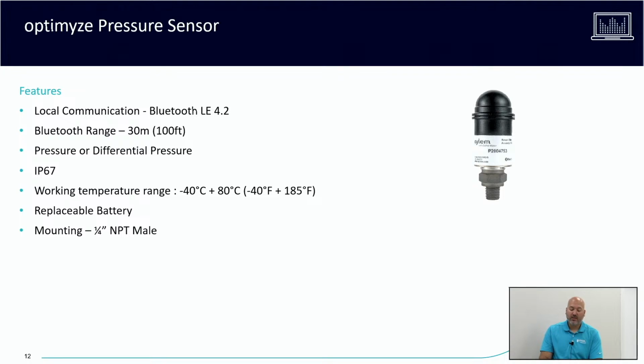Lastly, the pressure sensor. This is once again communicating via Bluetooth to the optimyze sensors. So the pressure sensors will have to be mounted or installed within 100 feet of the optimyze sensors to get that data over. As I touched on earlier, you could measure just suction pressure, discharge pressure, both, or even the differential pressure across the pump if you wanted to.